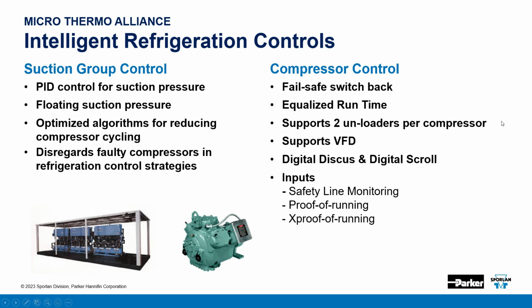We can support up to 2 unloaders per compressor. We support VFD, not just on the lead compressor, but we can have a VFD on every compressor on the rack. We also monitor and control digital discus and digital scroll. And as far as safety inputs, we have safety line monitoring. We have proof of running.